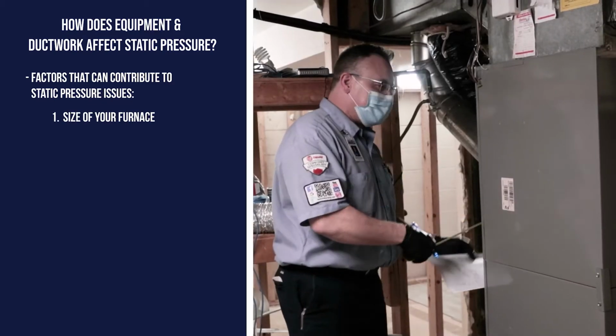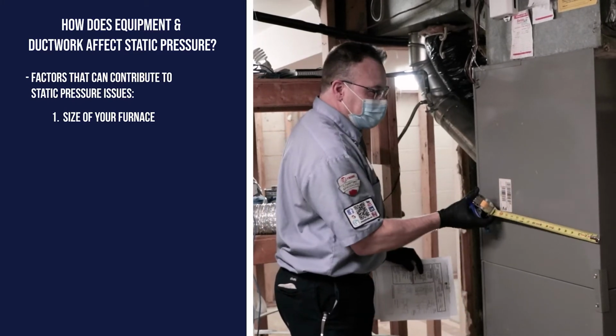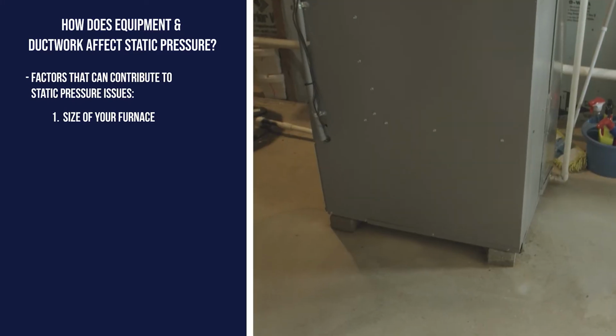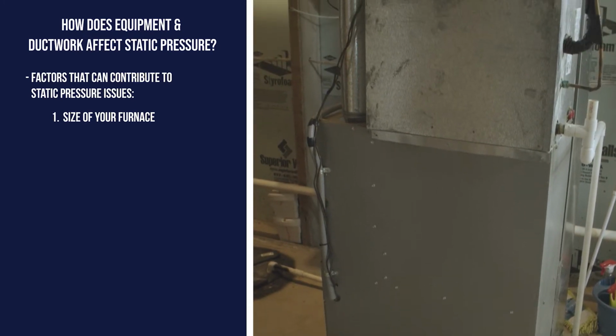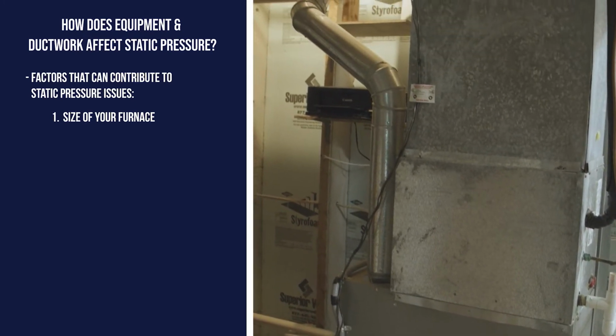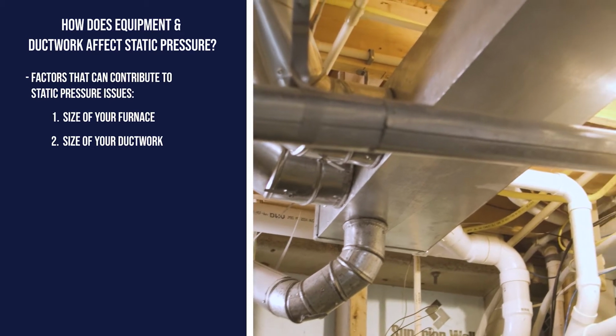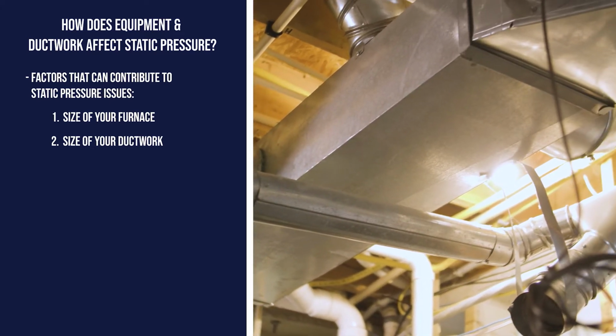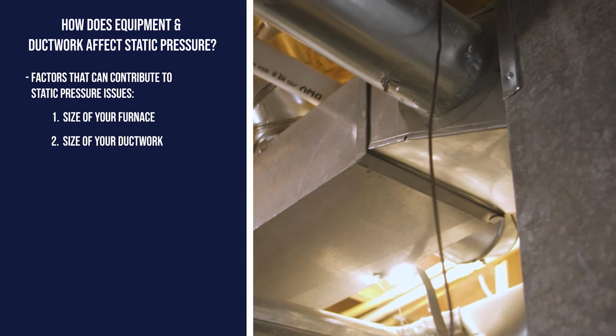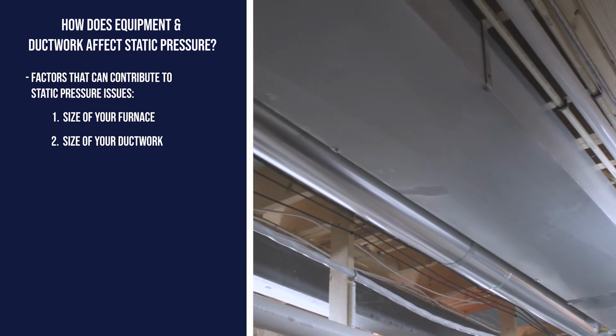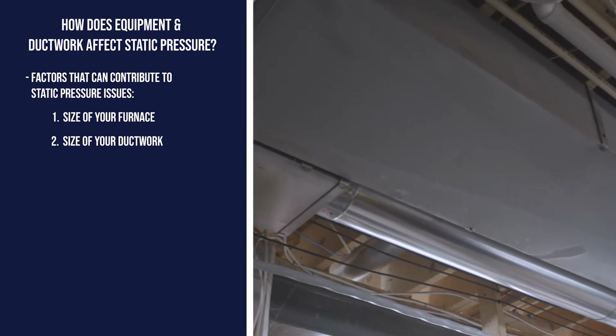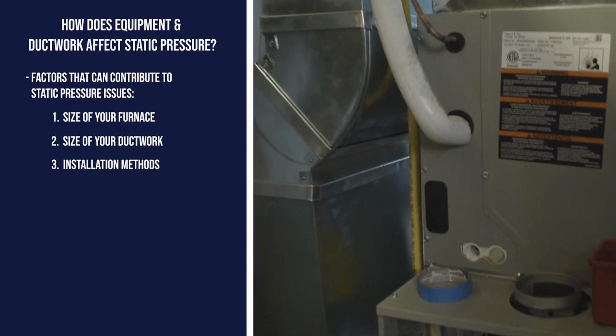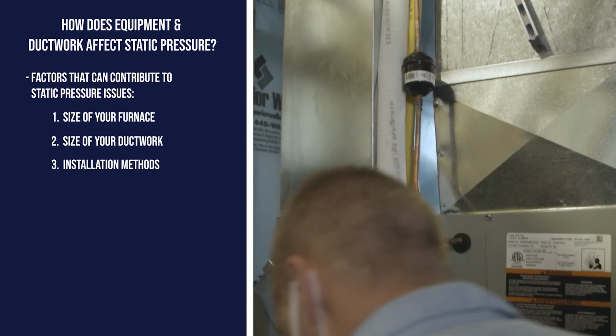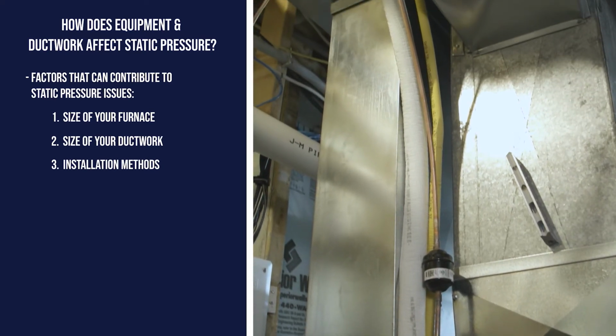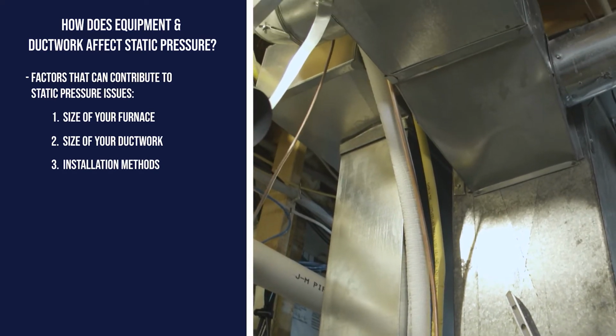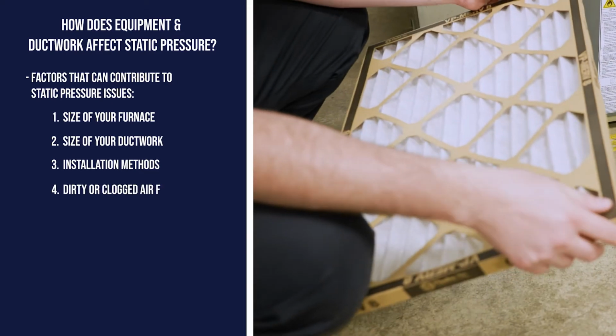An oversized furnace can be too powerful and can cause high static pressure inside your ductwork, while an undersized furnace won't be able to move enough air throughout the system to keep you comfortable. Second is the size of your ductwork. If the ductwork in your home is too small, the air moving inside can become too restricted and cause high static pressure. Conversely, if your ductwork is too large, the static pressure becomes too low and can rob you of your comfort. Third is the installation of equipment and ductwork inside your home. Improper installation or too many bends and turns in your ductwork can negatively affect static pressure levels. Fourth is a dirty or clogged air filter.